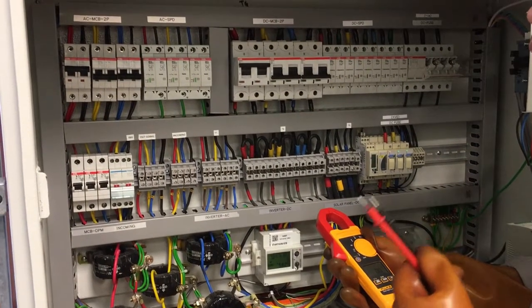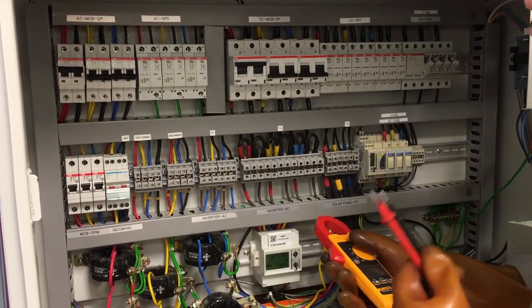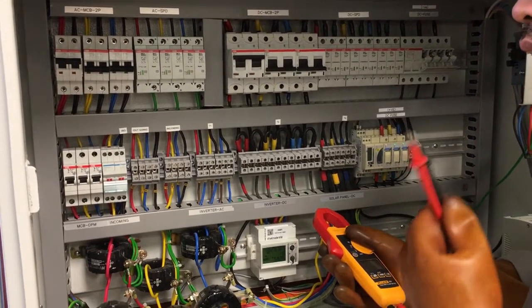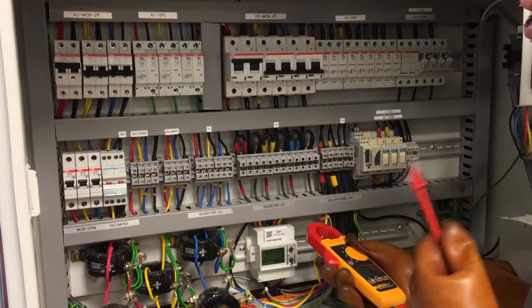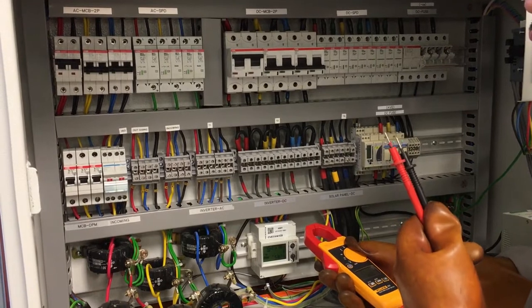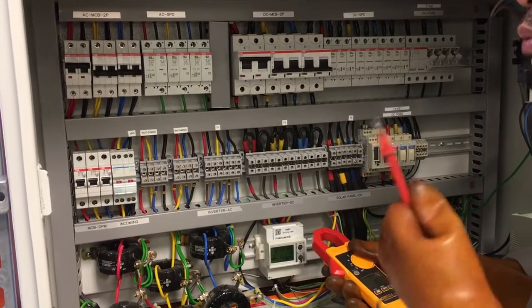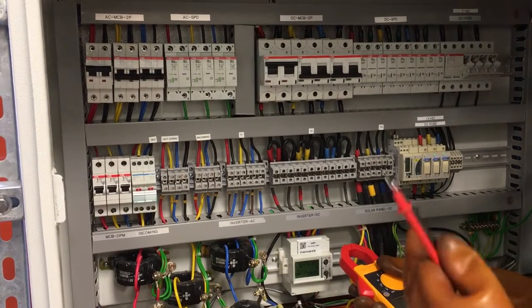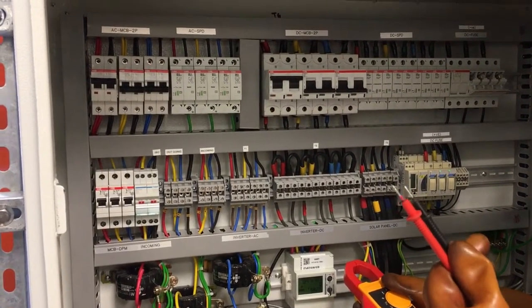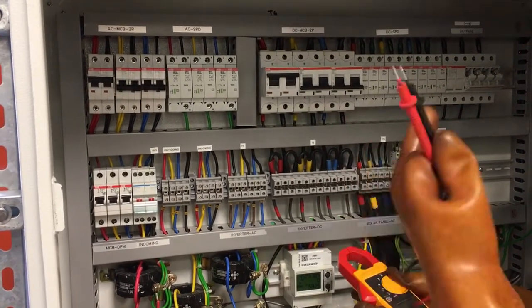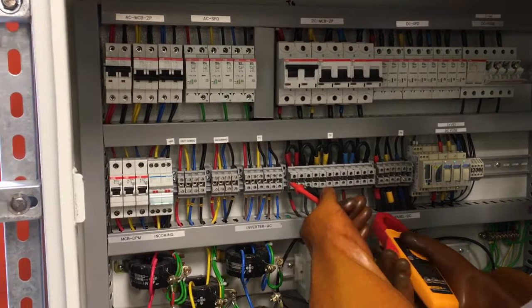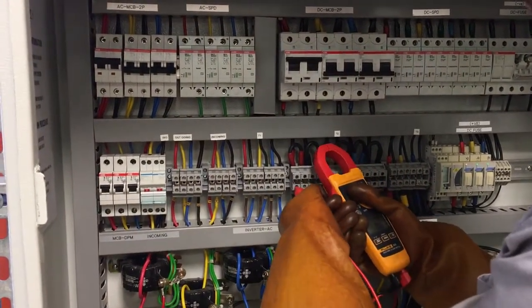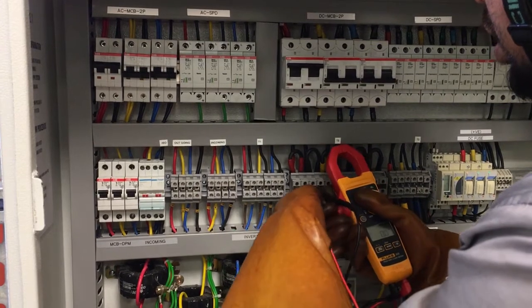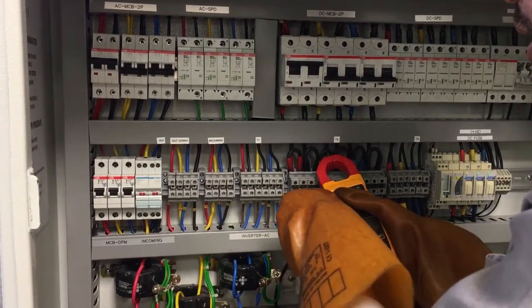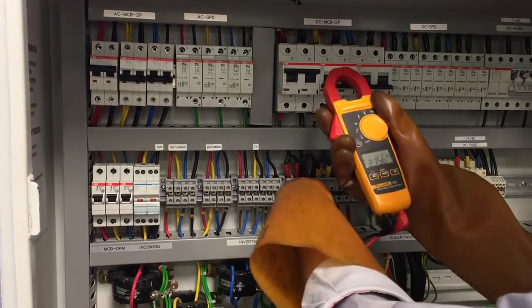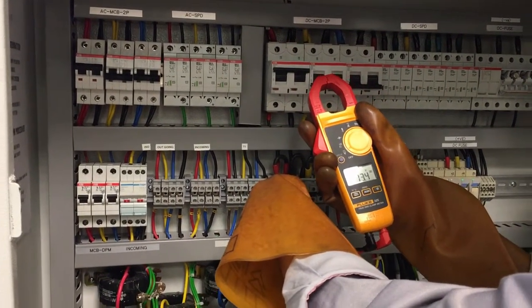Okay, now I want to demonstrate about what we call as anti-islanding. Now, to recall, anti-islanding is when the power from the grid is off or is not available or is out of range. We want our inverter to cut off the supply. We do not want our inverter to supply to the grid under those conditions for safety purposes. Okay, so now the system is turned on. So let us measure the DC voltage. Okay, the DC voltage is now 217.